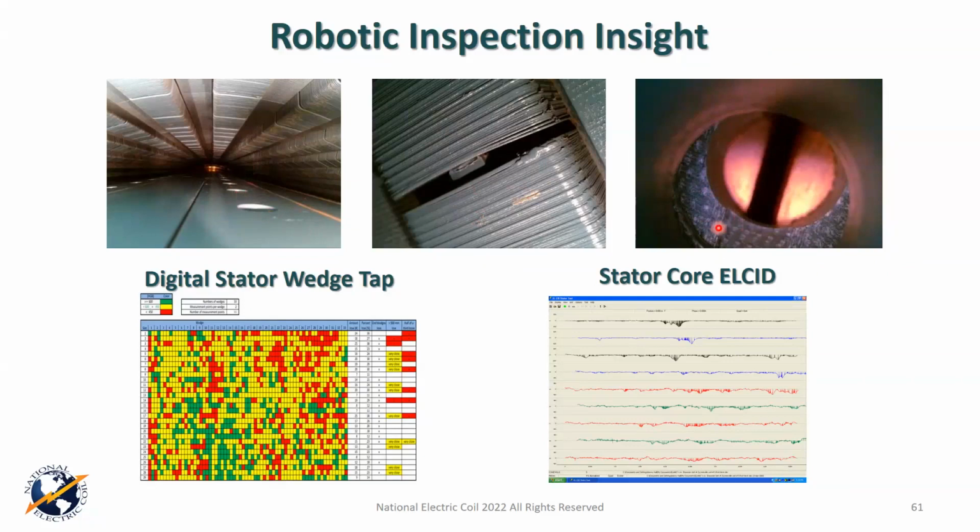And there are fixes on this. This is a common problem on some of the 7FH2s that haven't had the modification to the rotors. Two other things that it can do, and these are options. Normally, if you go to get a robotic inspection, you get a question about the ELCID on the 7A6 units. I'm sorry to tell you, no. The 7A6, it cannot.